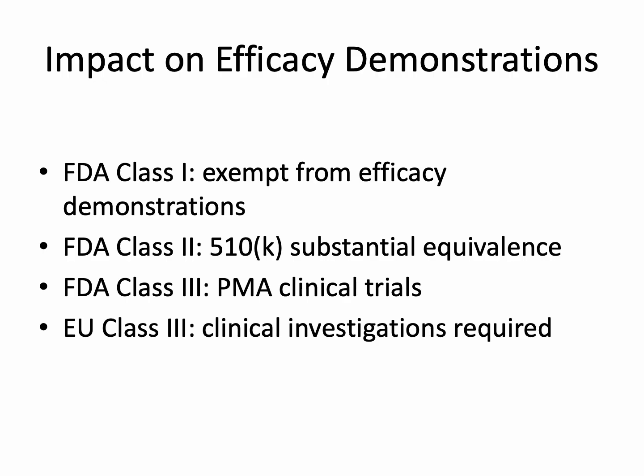FDA Class 1 devices are generally exempt from efficacy demonstrations, whereas Class 2 devices must show substantial equivalence to predicate devices via the 510(k) pathway. Class 3 devices require pre-market approval, PMA, supported by clinical trials demonstrating safety and effectiveness.